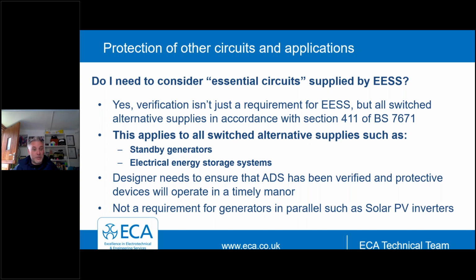Well, yes, we need to ensure that we've got the correct earthing systems in. And typically, these would be TN-S systems, okay? And it's worth confirming that with the manufacturer and making sure you've got that neutral-earth relay or bonding in place. But we still need to consider, are our protective devices going to disconnect? Now, often with power electronics, small generators, battery storage systems, they don't quite have the oomph. They don't have the fault currents that we expect on our normal network. We're very blessed in the UK, believe it or not. We experience very high fault currents on our network, which gives us those really low fault loop impedances and rapid disconnection. If you do a protection study on most devices, you'll find they are clearing faults well under 0.1 seconds. They don't go to the 0.4 or 5 seconds that we're accustomed to.